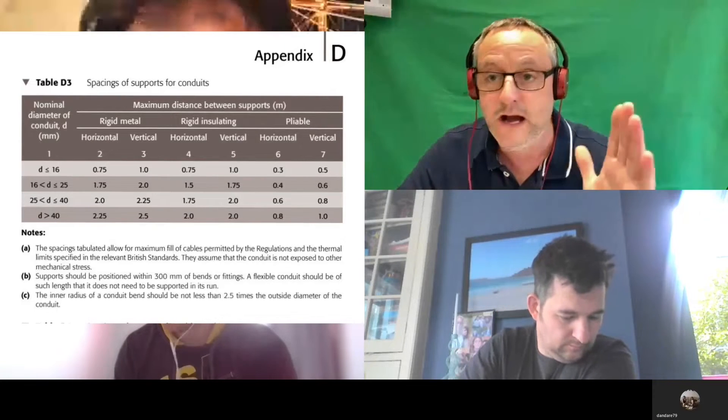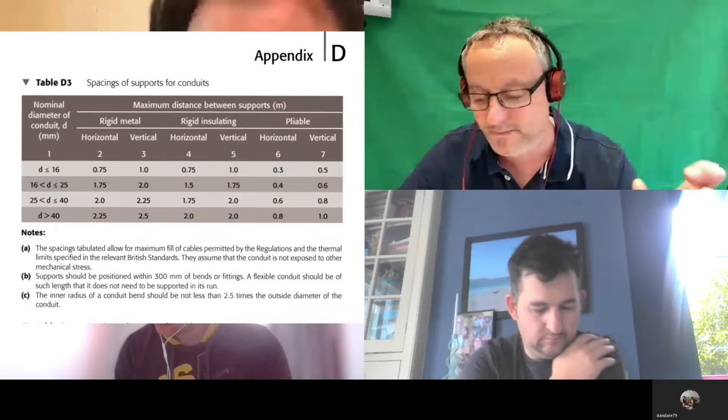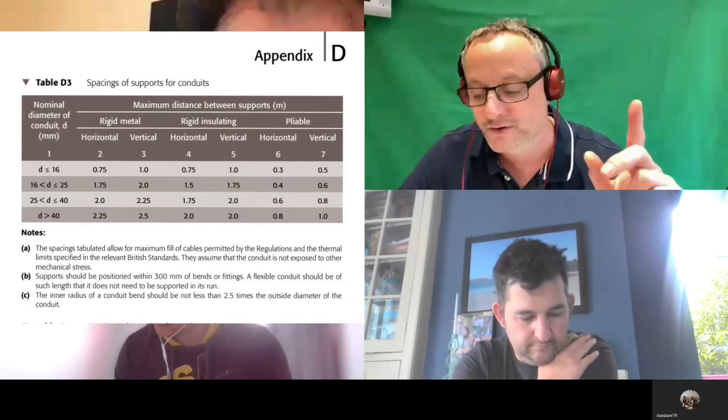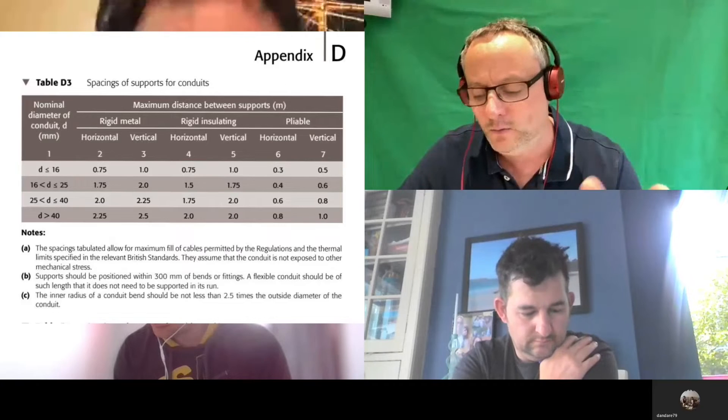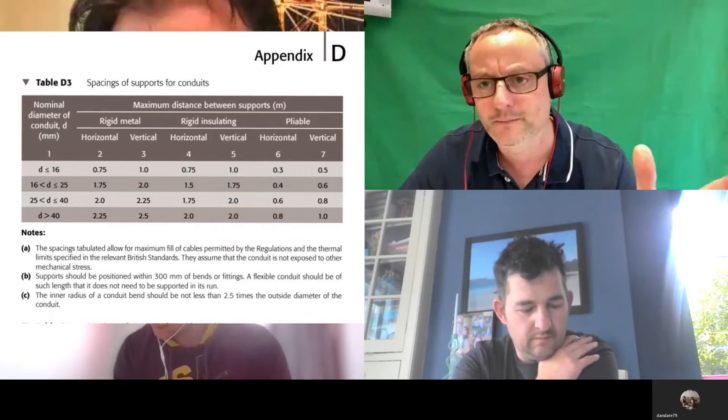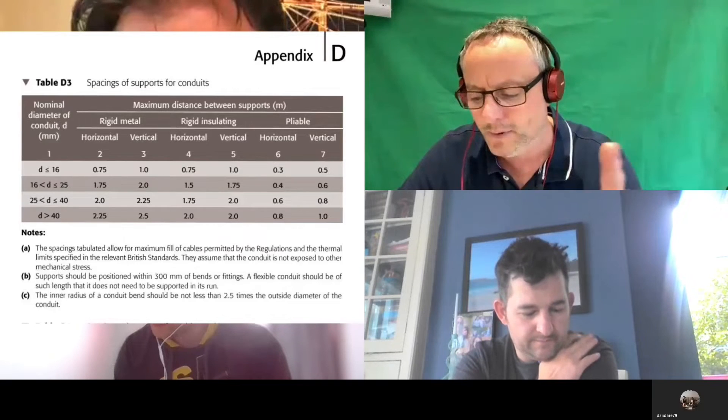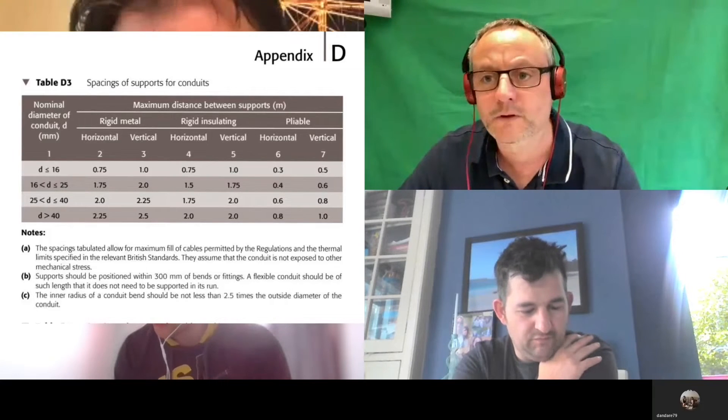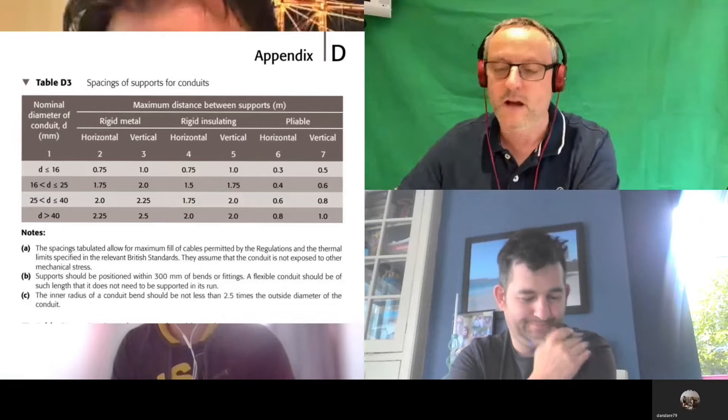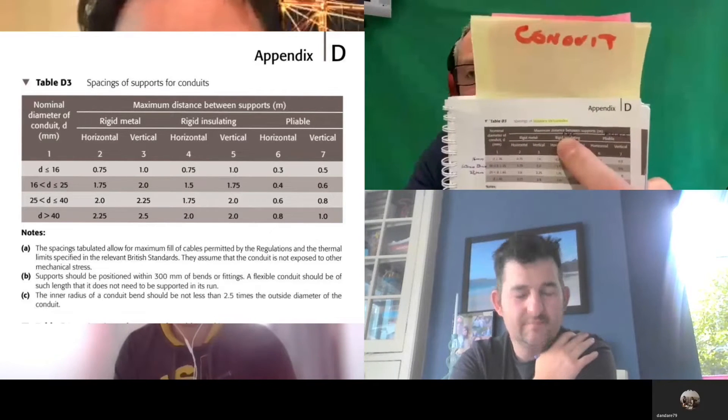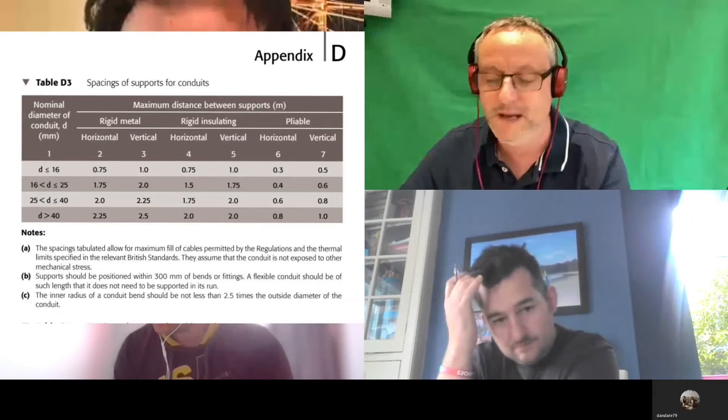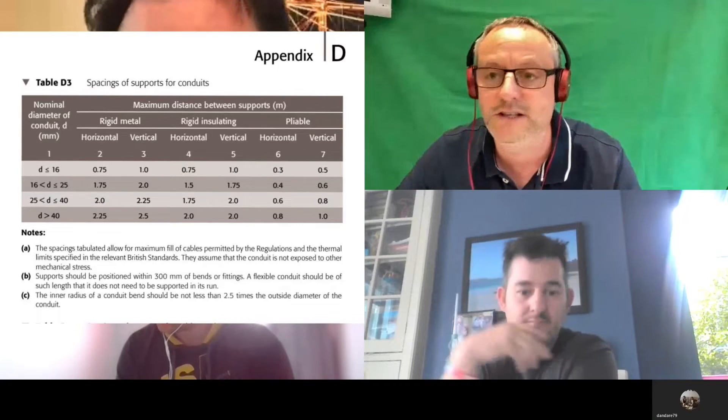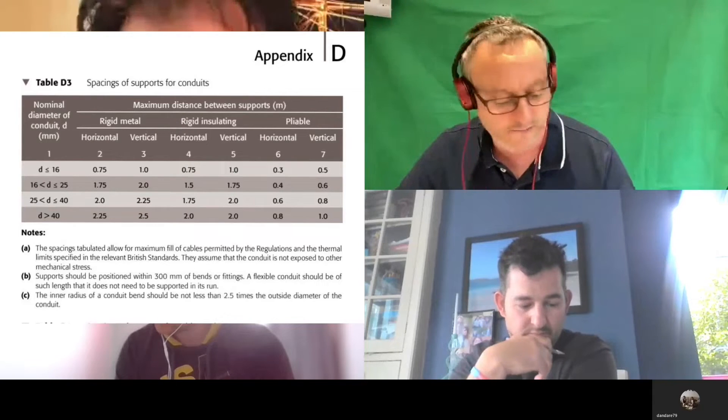I've highlighted the top of the page where it says it's for conduit, just in case I forget when I come back. If I was fixing a conduit that was 16mm in diameter and it was plastic, which columns am I going to use? Column number one for plastic conduit, four or five. But what it doesn't say is plastic—what does it say? It says rigid. I think last time I just got us to write the word PVC above it.